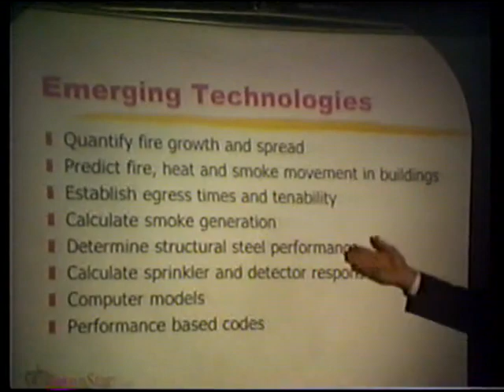It's amazing what you can do when you change from a standard sprinkler head to a quick response sprinkler. You can change your whole fire profile dramatically. Test data shows it. We can now quantify it engineering-wise, so we don't always have to have a fire test.